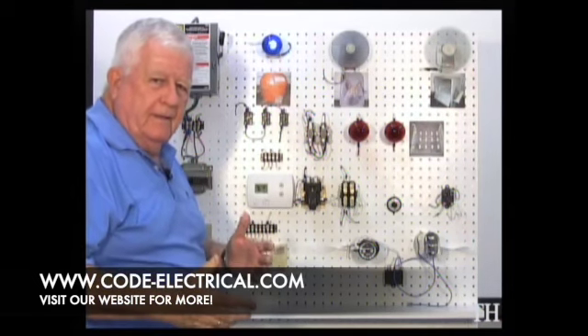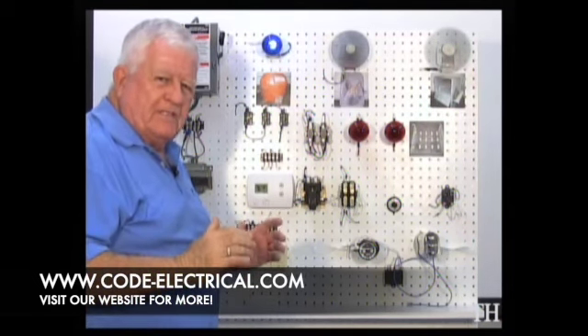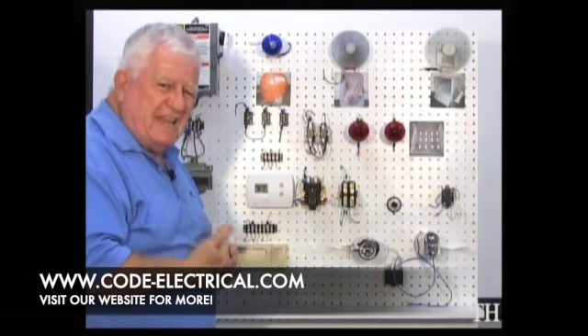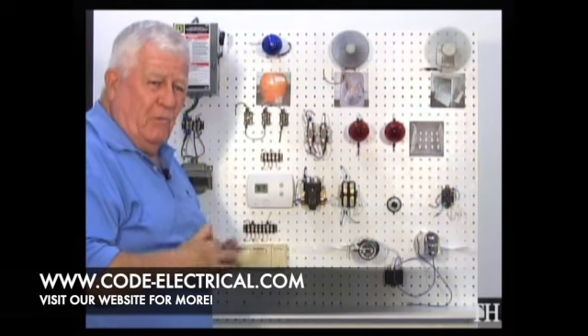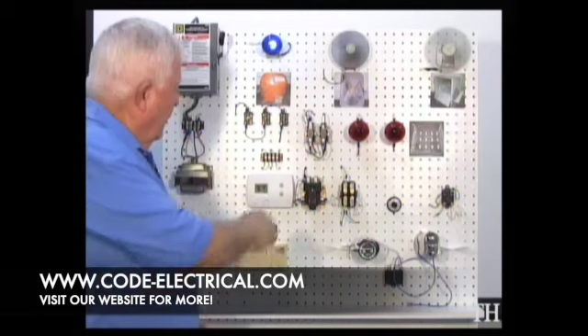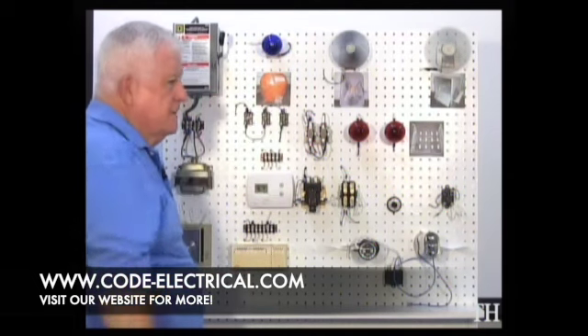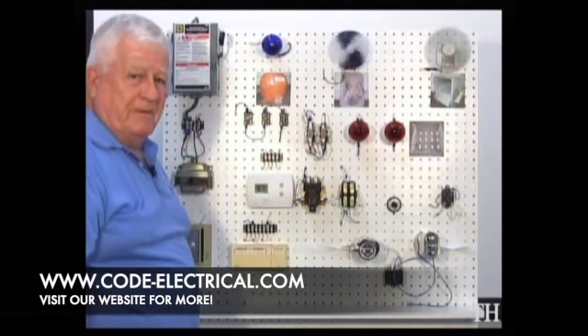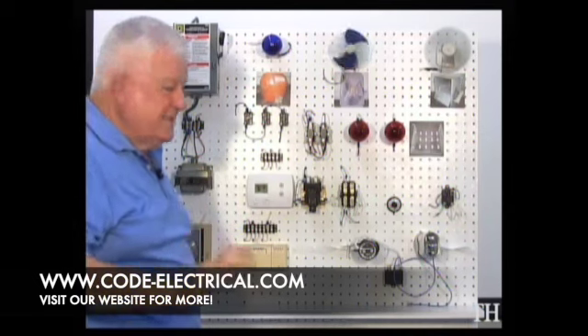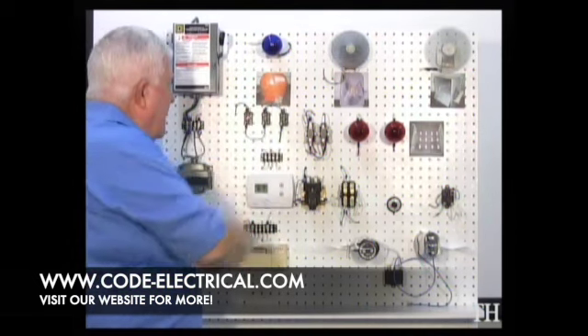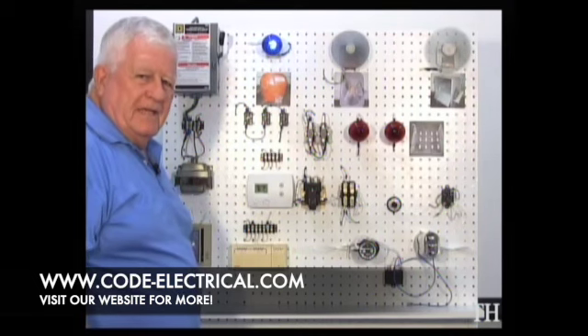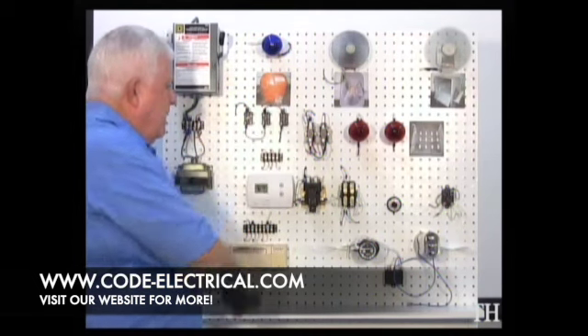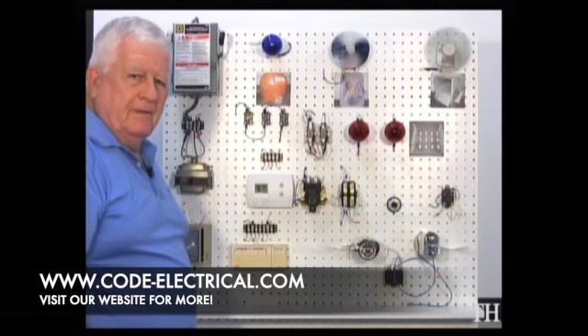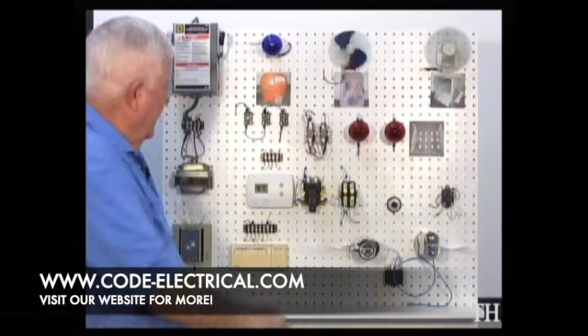Compressor's running. But as you're going to learn on the schematic, and when you troubleshoot, say the compressor isn't running, or it runs and it stops. What if it's a high pressure switch? That stopped it. Remember, they're in series. Or say it's all right, but guess what? I got a low pressure problem. It stopped it.